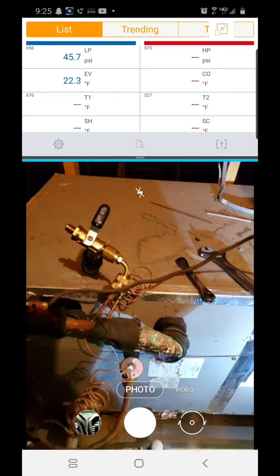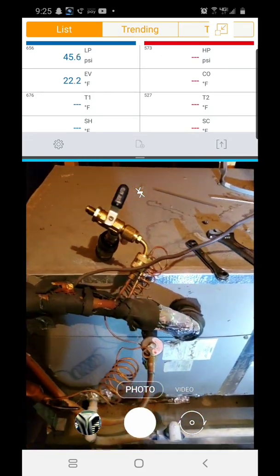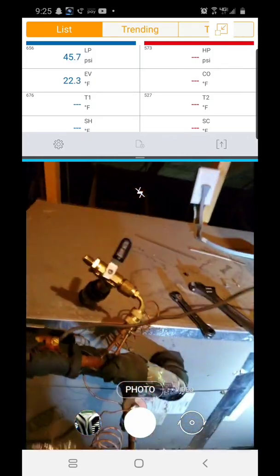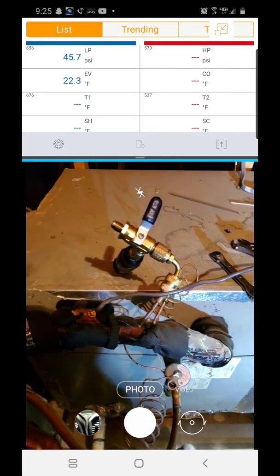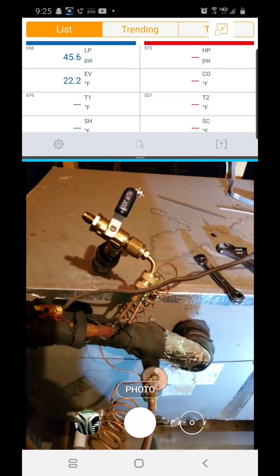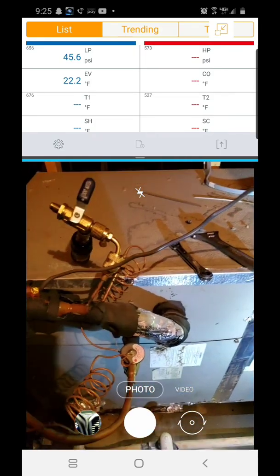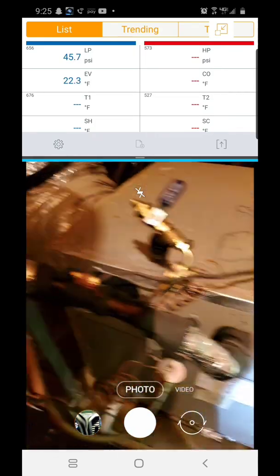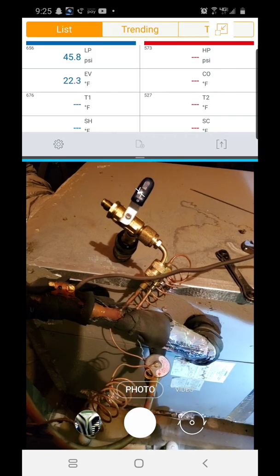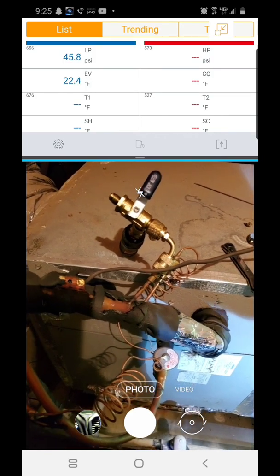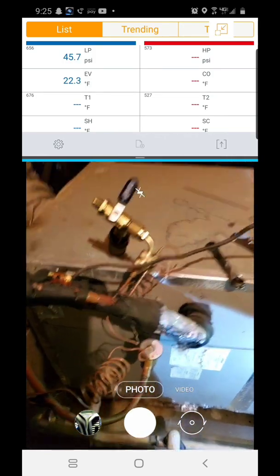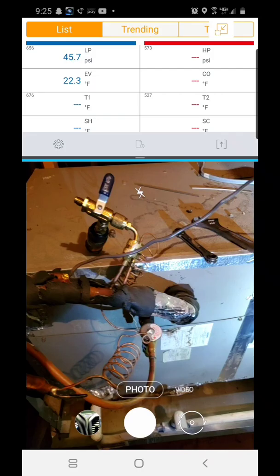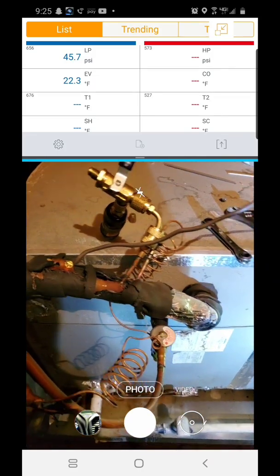So I actually put my gauges on it and it was down to like 18 psi. Tried to add a little bit of extra charge but it just started stacking up, didn't get much over 20. I tried to reverse the reversing valve a few times. It kind of felt like it was starting to cool for a second and then didn't. So now I'm up in my attic at 9:30 at night.